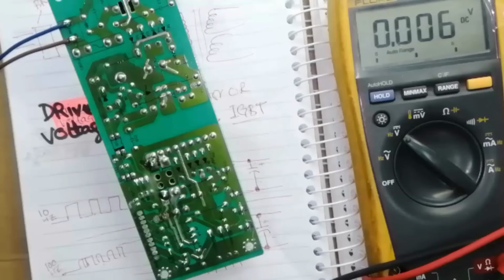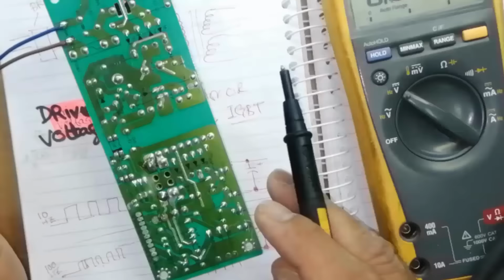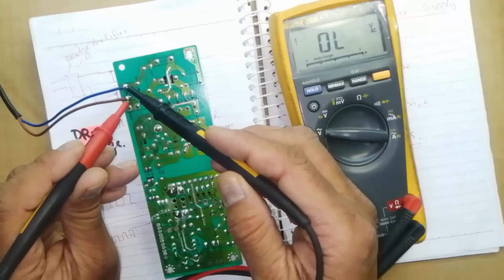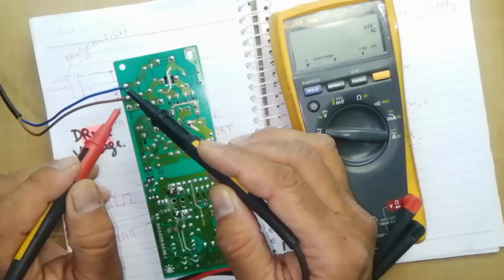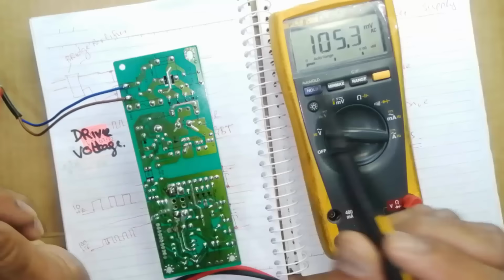Now what happens if this power supply is not working? What we will do in the first stage, you have to check AC voltage here. It's 230 volt. If I cannot find voltage here, I have to test the lead. If the input voltage is not appearing here, I have to check the input cable.